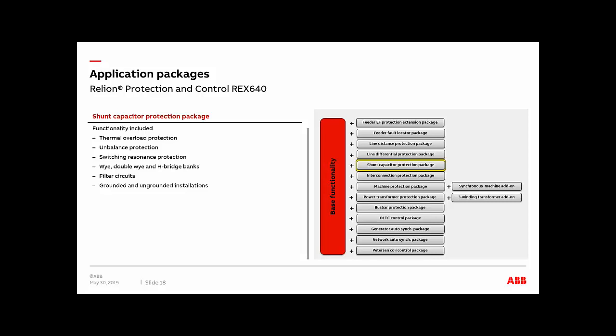So it can also be applied for banks that are used as filter circuits. It's also another possibility there with the settings. We can define what type of capacitor bank we're protecting and take special measures into account. It's important to say here that you can use unbalanced protection for capacitor banks that are internally fused, externally fused, or fuseless. It doesn't really matter. You can use them on all types of fusing in capacitor banks.